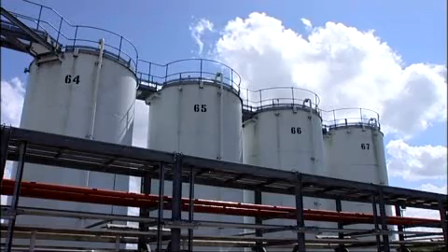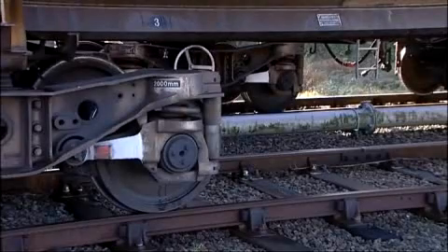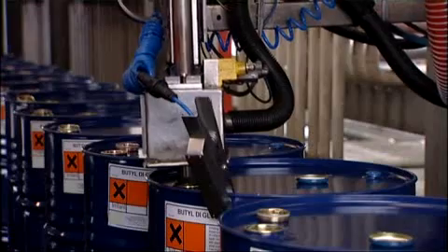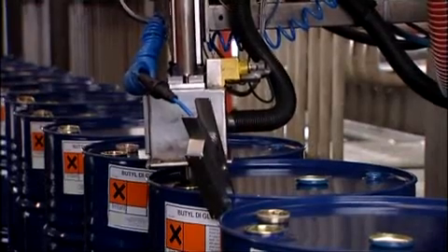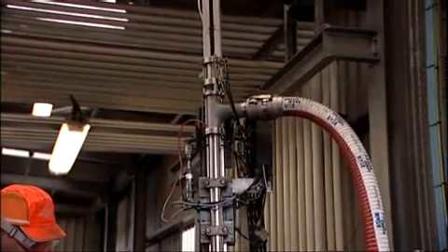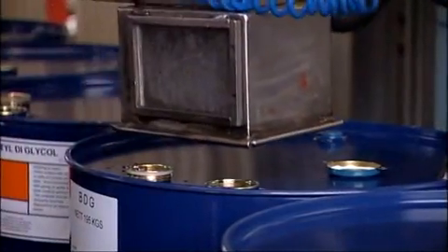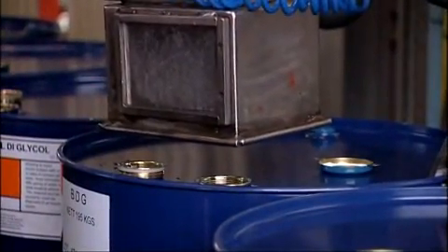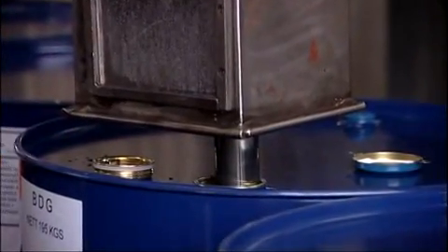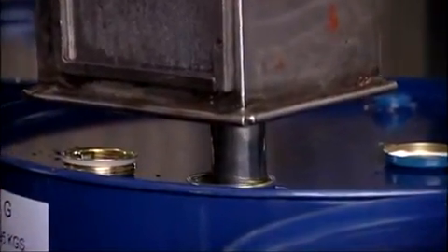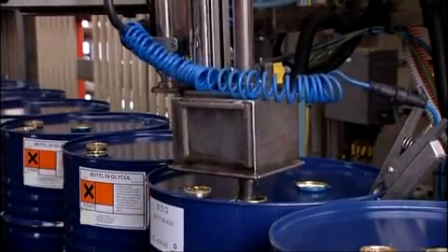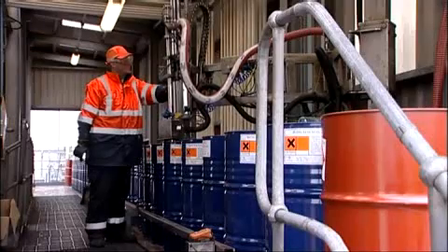During filling operations of tanks, road tankers, rail cars, ships, IBCs, drums and cans, splash filling and free fall of flammable liquids should be eliminated to the maximum extent practical by providing diverters to discharge the liquid down the side of the earthed container, or by submerging the fill pipe below the liquid level to the bottom of the vessel. Incoming velocity should be reduced until the pipe is below the surface of the liquid.